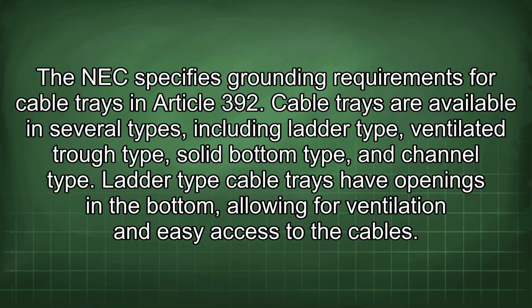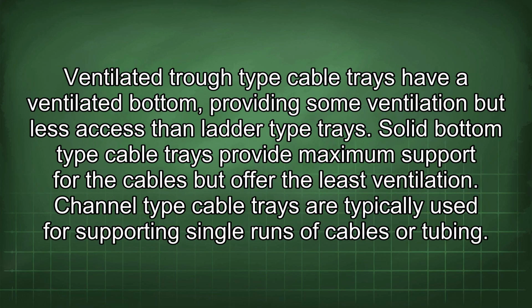The NEC specifies grounding requirements for cable trays in Article 392. Cable trays are available in several types, including ladder type, ventilated trough type, solid bottom type, and channel type. Ladder type cable trays have openings in the bottom, allowing for ventilation and easy access to the cables. Ventilated trough type cable trays have a ventilated bottom, providing some ventilation but less access than ladder type trays.